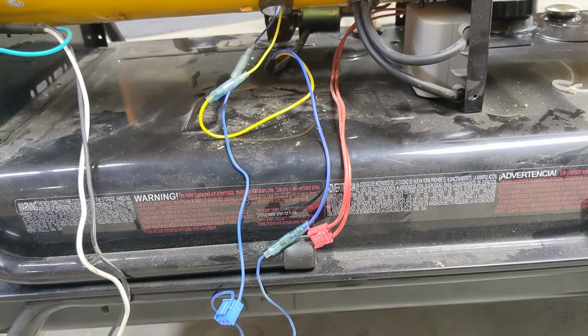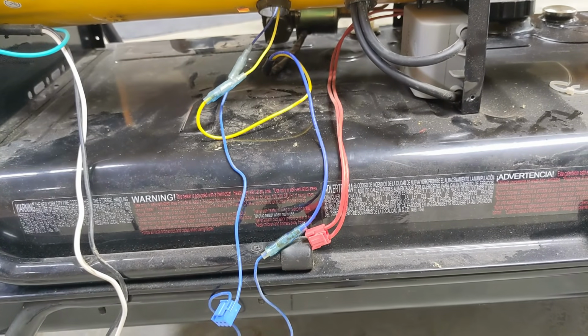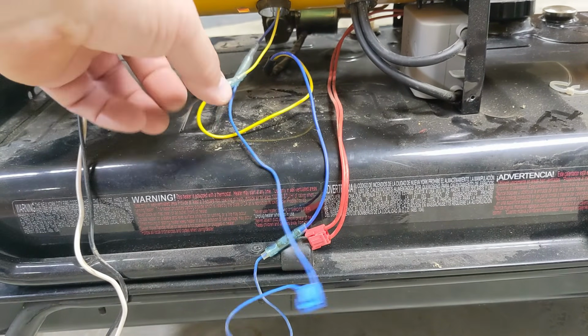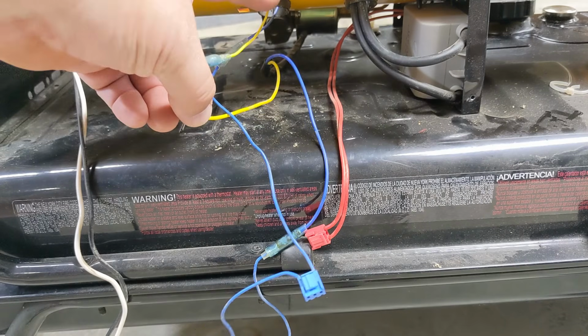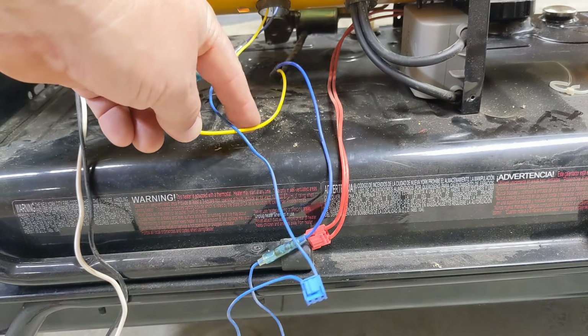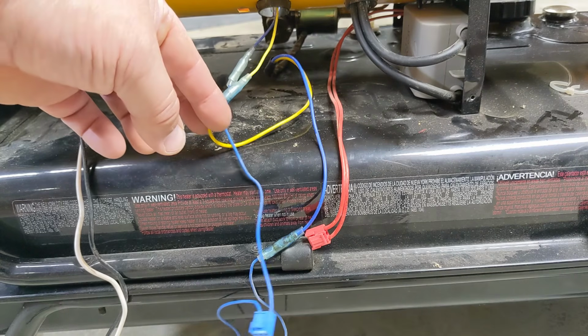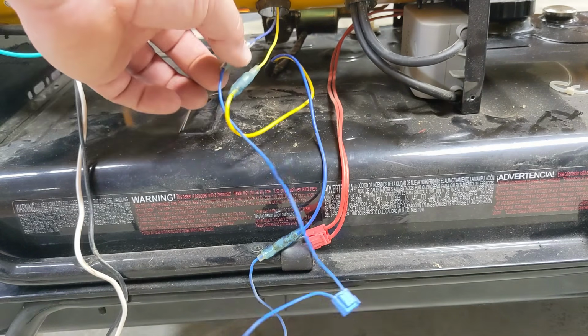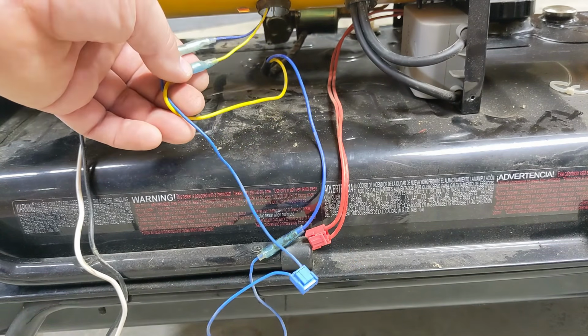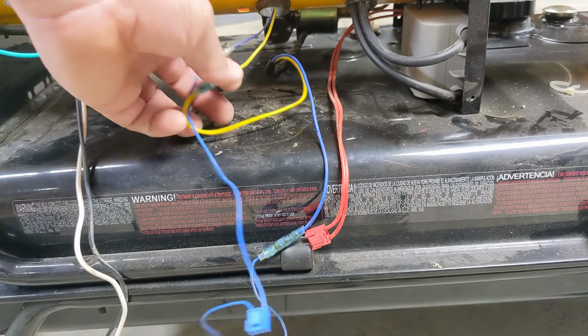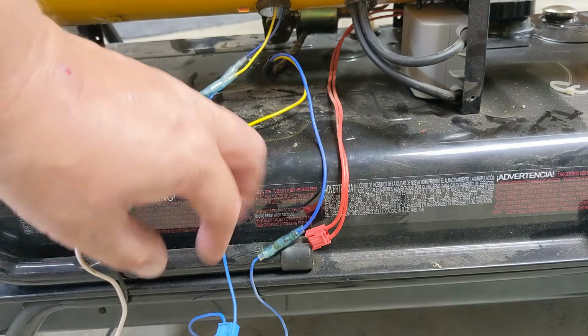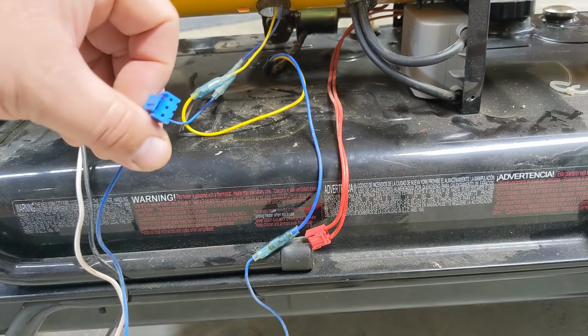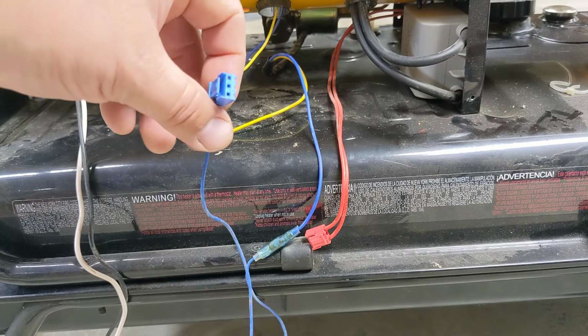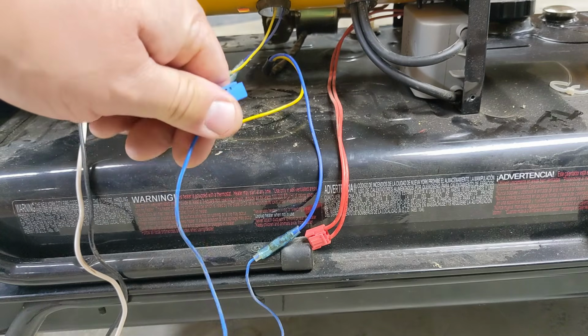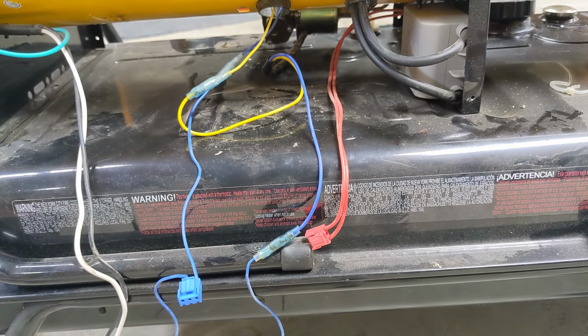I need to take that cover off and find out. And I suspect then that it feeds AC, one half of it, over to the fuel pump, right? And the blue wire also goes up to that motor. So I think the yellow is one side of the AC connection, the blue is the other. The blue goes through that sensor, and I bet you that this blue connector then is normally 120 volt when the machine is on and running.